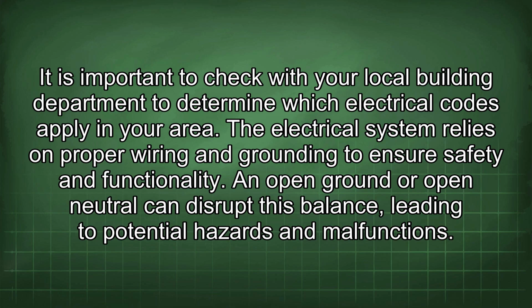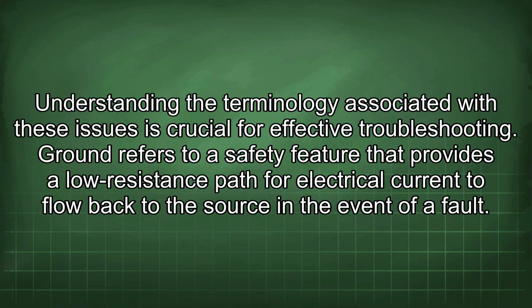The electrical system relies on proper wiring and grounding to ensure safety and functionality. An open ground or open neutral can disrupt this balance, leading to potential hazards and malfunctions. Understanding the terminology associated with these issues is crucial for effective troubleshooting. Ground refers to a safety feature that provides a low resistance path for electrical current to flow back to the source in the event of a fault.